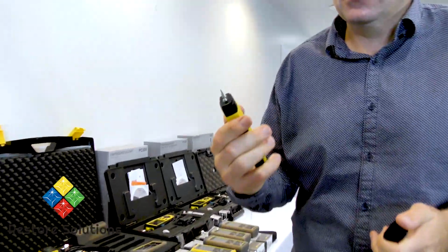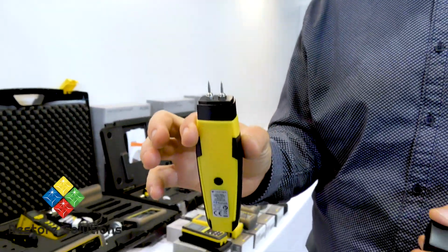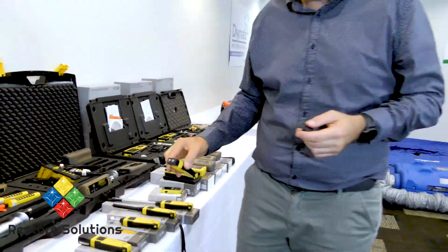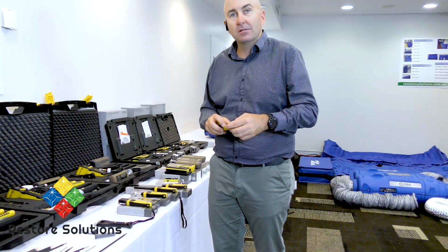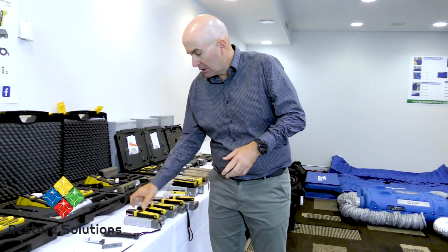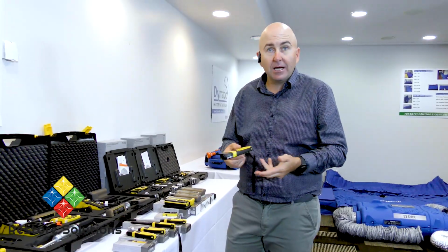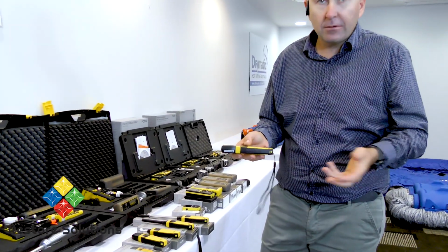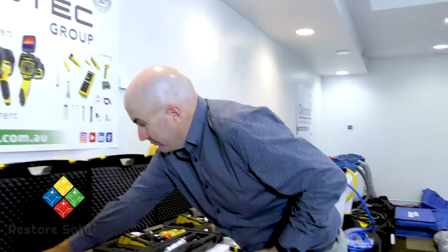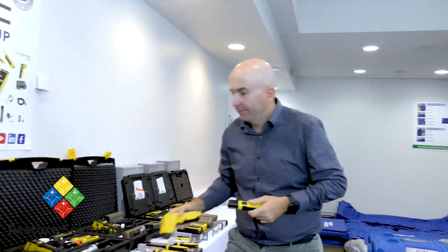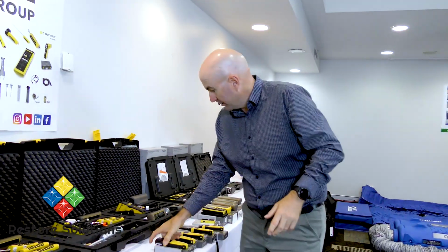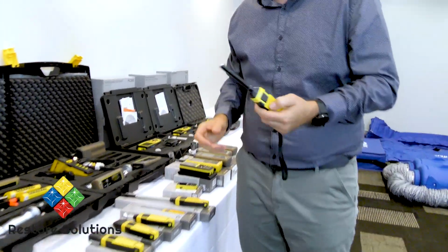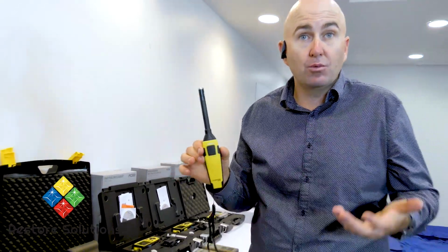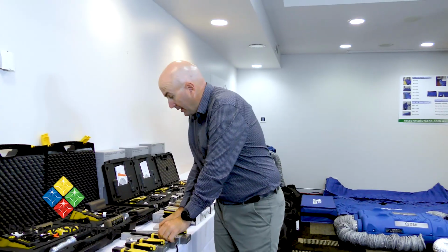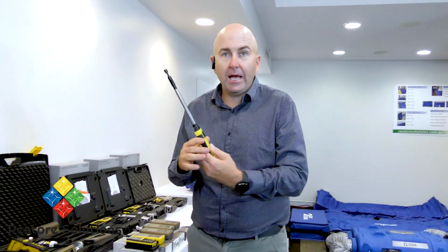Well, I have a pin meter. Okay. It's only basic. There's no hammer probe attachment, no long probe. So these are not going to replace all your meters, but these are a great quick test if you want to go out and check jobs. Then you've got a laser, a multi-laser gun, just like the laser gun here. What else do we have? We have a hygrometer to check your temperature and your relative humidity. And we have an anemometer, an airflow meter, to check your airflow of your jobs.